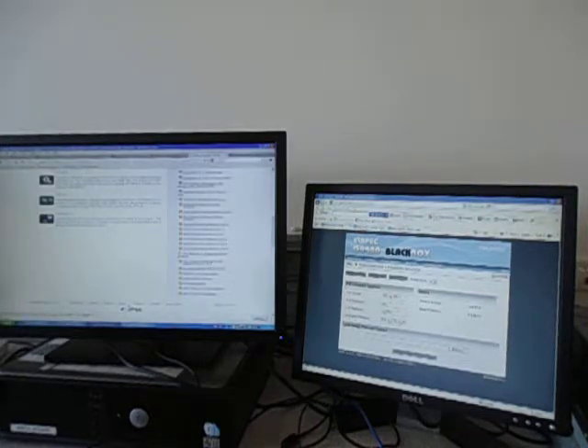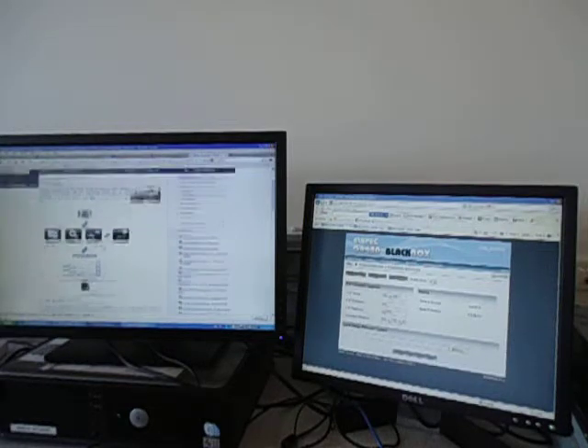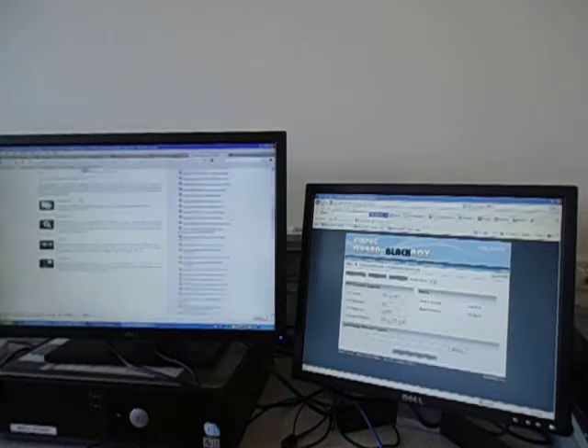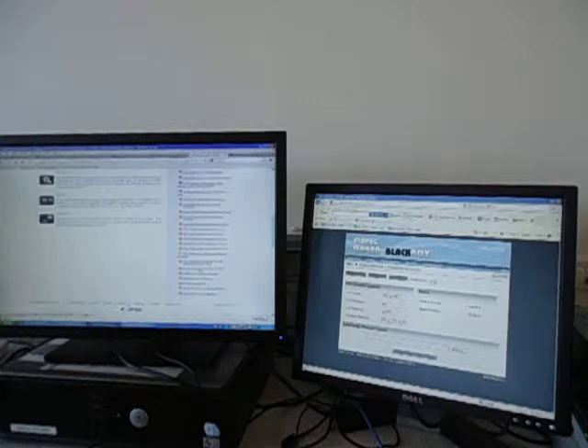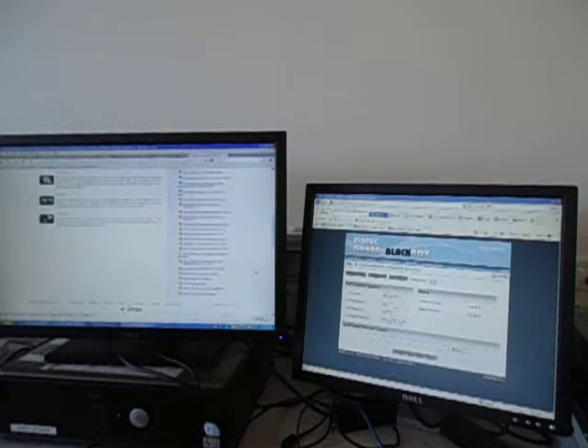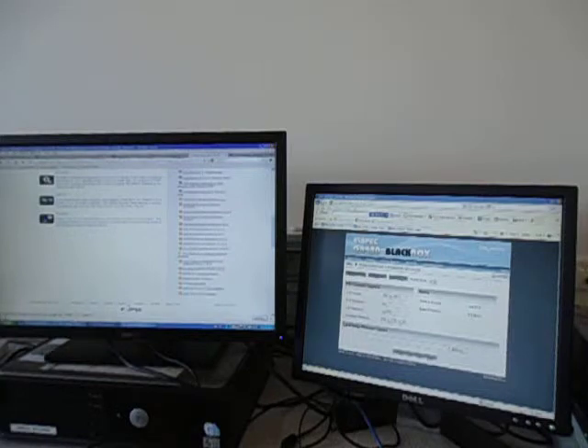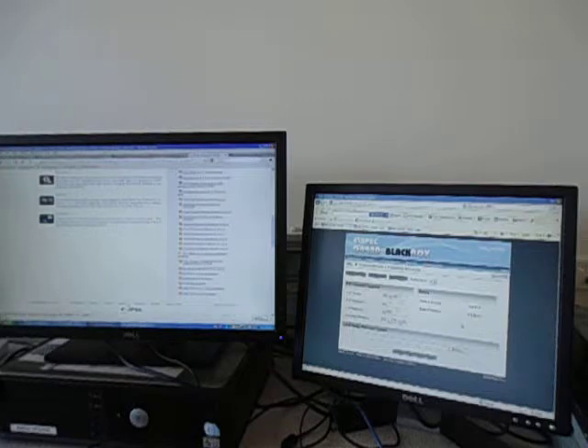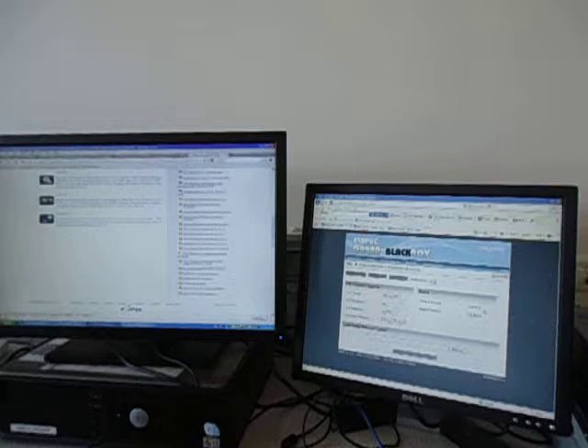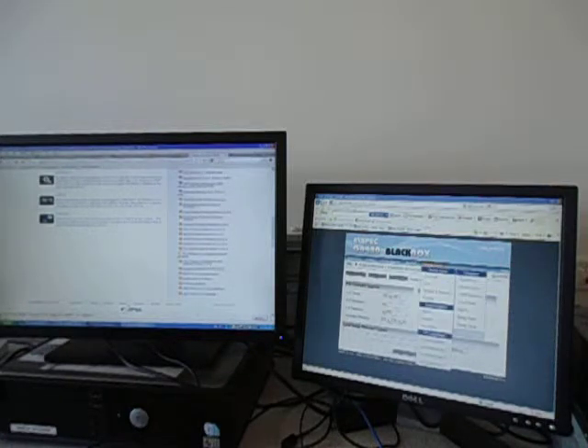It's easy, you just browse to download the latest firmware from the Elspec website. This is Elspec PQ SCADA and down here you can see the firmware software version 4.07.0, which will change as time passes. Download that to your computer, then you browse, upload it. It takes a while to update. You can see here on this one the old version was 0.3 0.5 and this is 0.4 0.07.